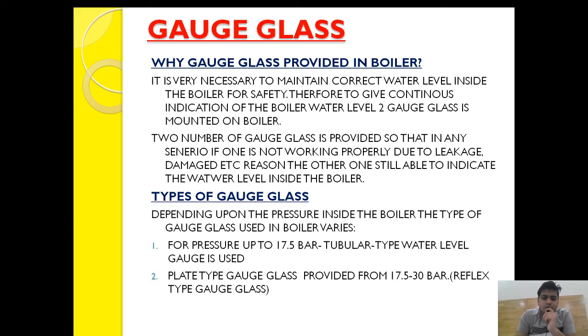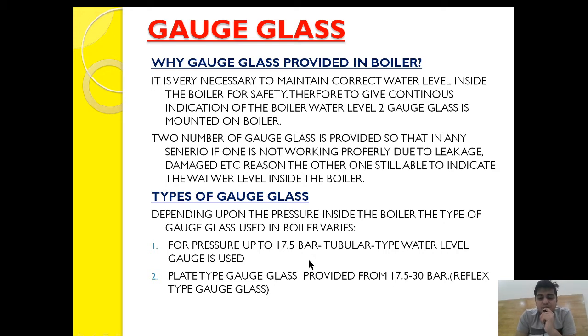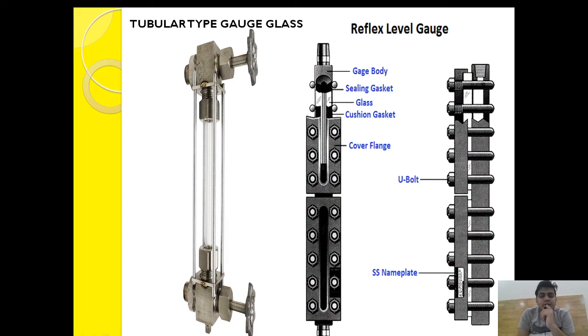Now let's see what types of gauge glass are provided in a boiler. Depending upon the pressure and type of the boiler, the type of gauge glass changes — as pressure and temperature increase, the gauge glass type changes. For example, for pressure up to 17.5 bar, a tubular type water level gauge glass is used. If the pressure is higher, a plate type gauge glass — mainly the reflex type — is used. Above 30 bar, other types are also used.